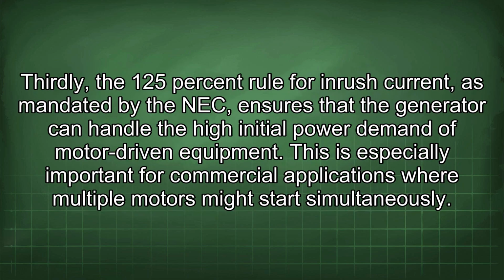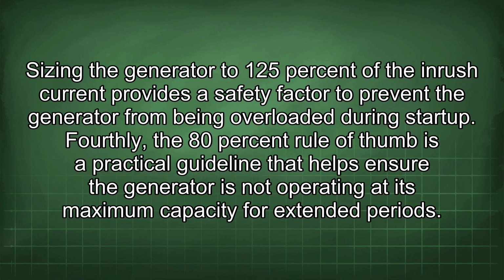Thirdly, the 125% rule for inrush current, as mandated by the NEC, ensures that the generator can handle the high initial power demand of motor-driven equipment. This is especially important for commercial applications where multiple motors might start simultaneously. Sizing the generator to 125% of the inrush current provides a safety factor to prevent the generator from being overloaded during startup.